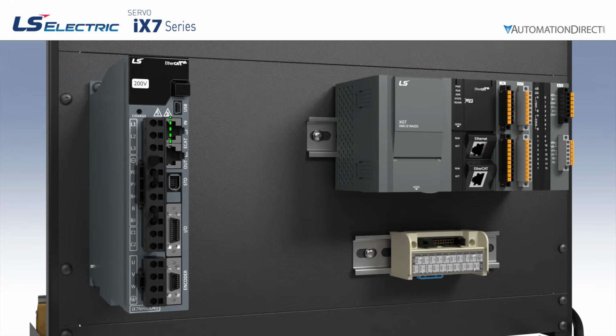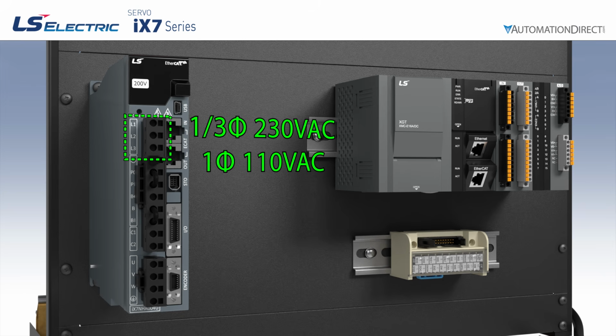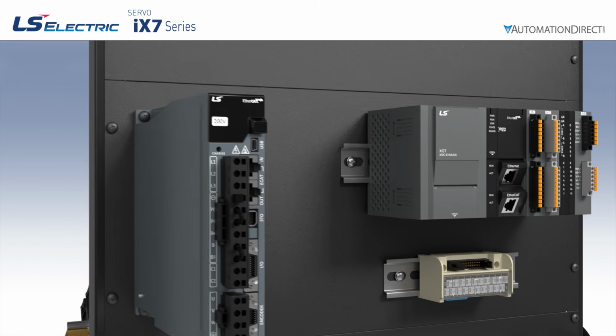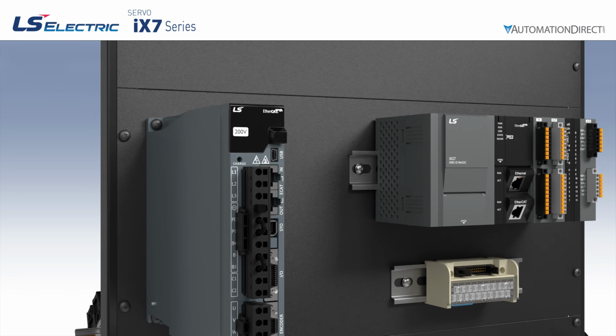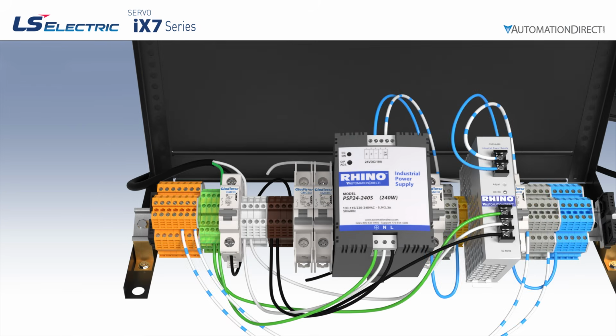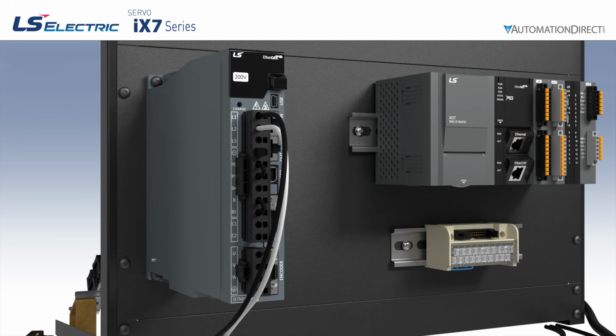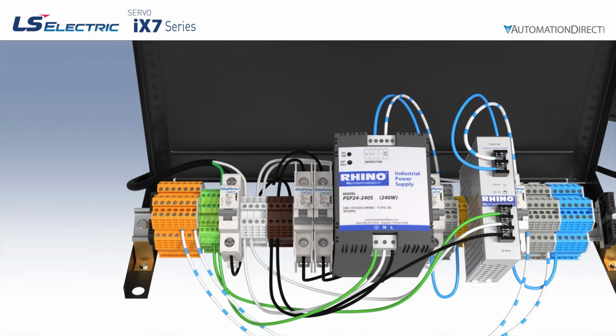For main drive power, all iX7 models accept single or 3-phase 230-volt AC. The 400-watt model can also use single-phase 110-volt AC by setting bit 15 of parameter 0x2034 to a 1, which is a decimal value of 32768. 110-volt AC is what we're using today. For single-phase wiring, you can use any 2 of the 3 power terminals, so we're connecting to L1 and L2 through a 15-amp circuit breaker. Control power connects at C1 and C2, and we'll run that through a 5-amp breaker. Make sure the PE earth-ground connection is secure.